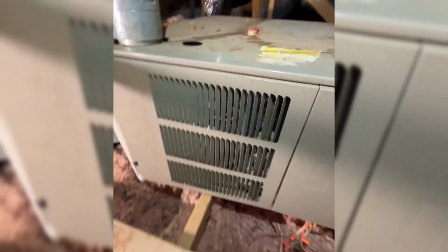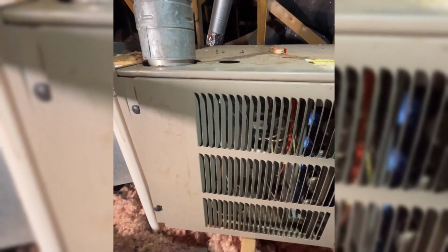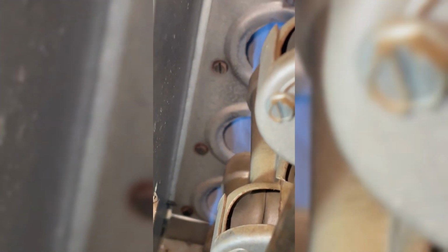This next one is actually one our technicians went on. It's a video, and it's kind of a funny thing when you first hear it. It sounds like Shakira should be in there doing a little dance or something. That thing is bouncing around in there. The heat exchanger has separated from its plate, and it's bouncing around in there doing some salsa or something. You can't really tell whenever that panel's on there, but on that second one where you're actually up close looking at the heat exchanger, it's definitely jumping around in there some.